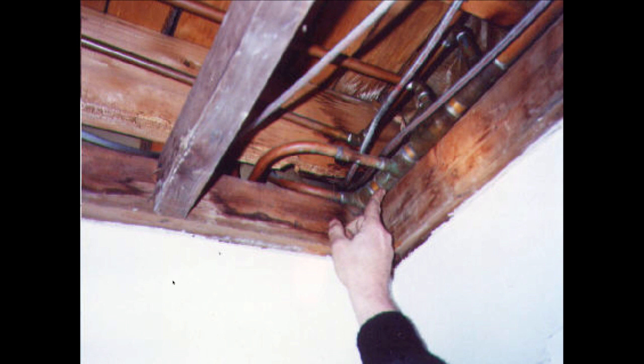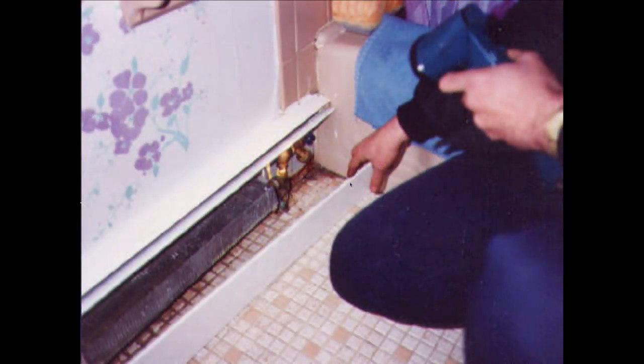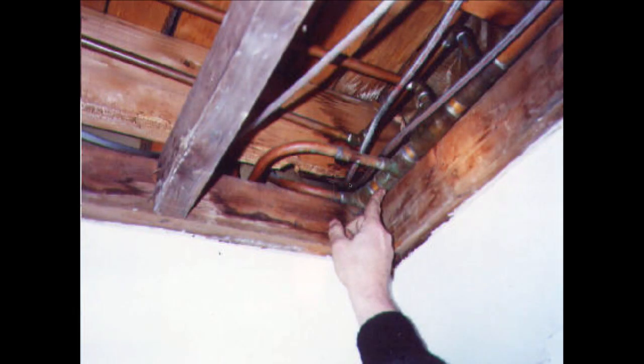This is back when he was still in his family's oil and contracting business. We were on this job in a person's house where Al was there because the boiler had actually dissolved and he was replacing it. Somebody else had done the work before him. But to figure out why they had no heat in this bathroom that was upstairs, he had to tear down the ceiling and we find this Diverter tee and a Standard tee. And this piping goes from here all the way upstairs to the bathroom and then it goes back down to where Al was.